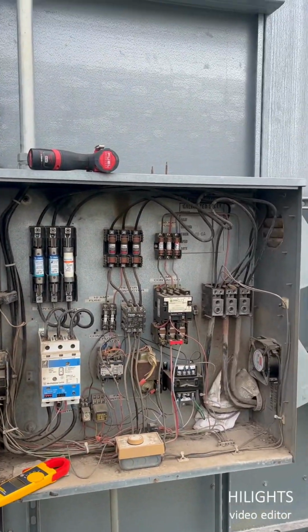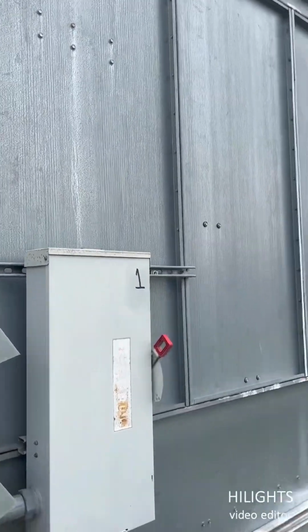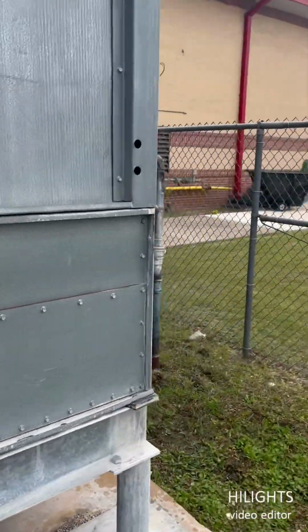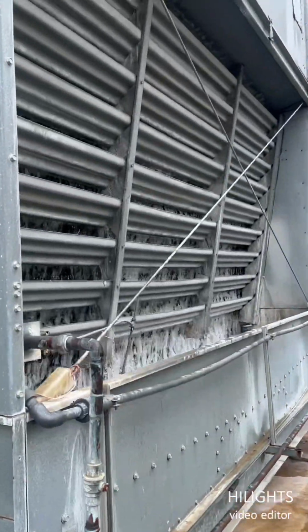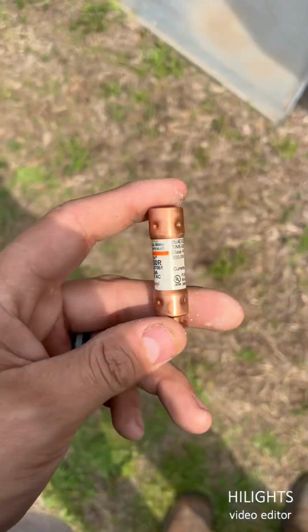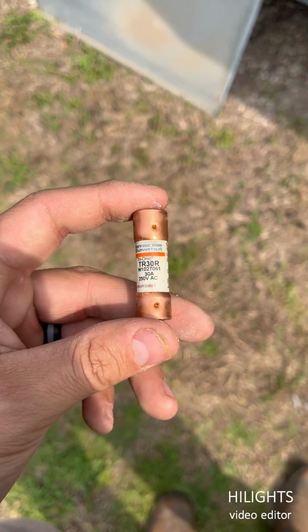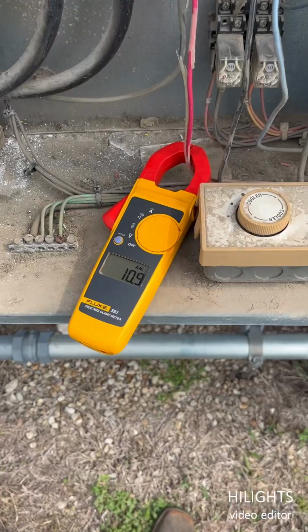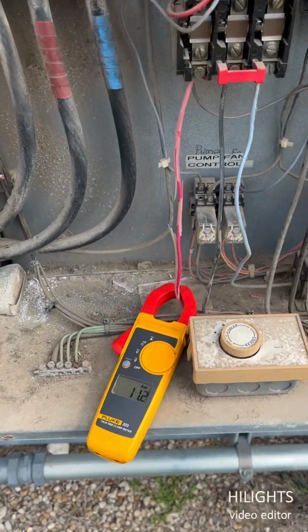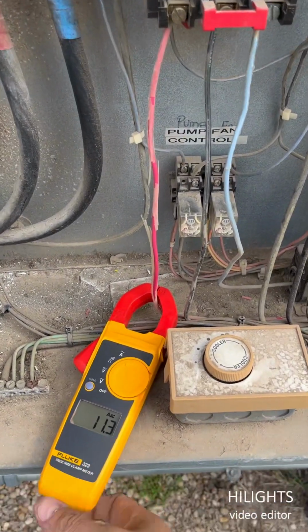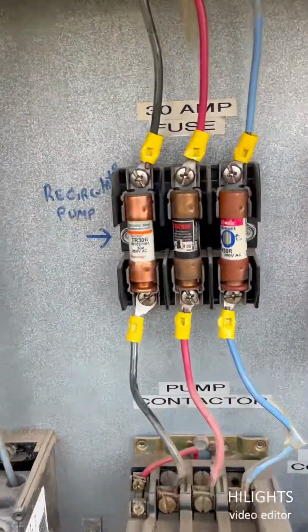Now good thing this school has 2 cooling towers, because the one right here is on, so at least the school is getting cooled down. But yeah, we need to address the other one. Got my fuse, let's pop her in. Good, reading 11 amps, which is good. I also replaced the connections.